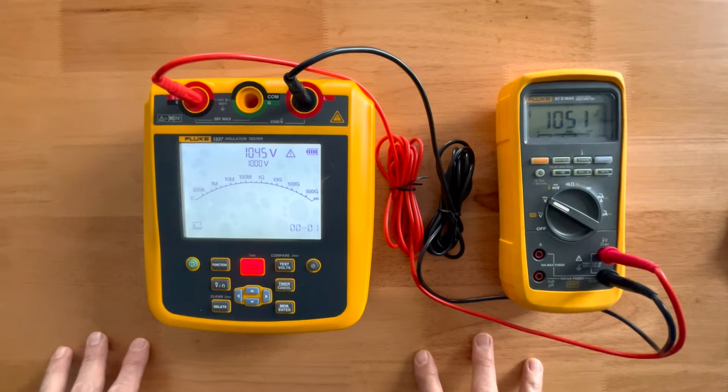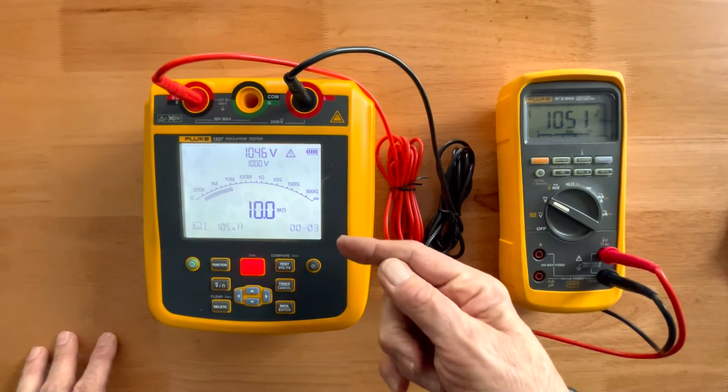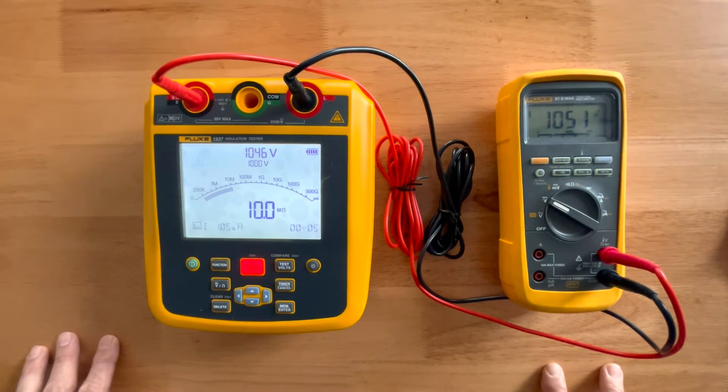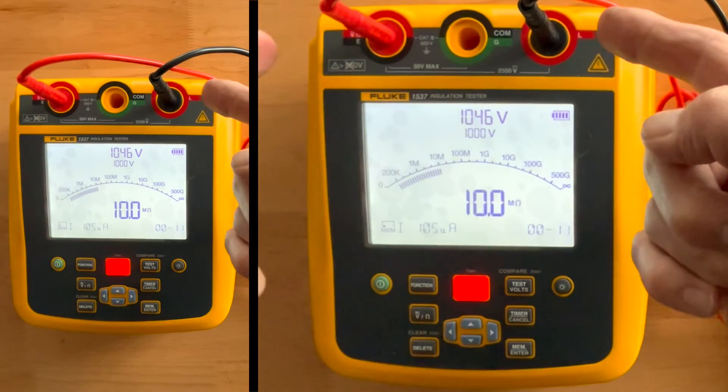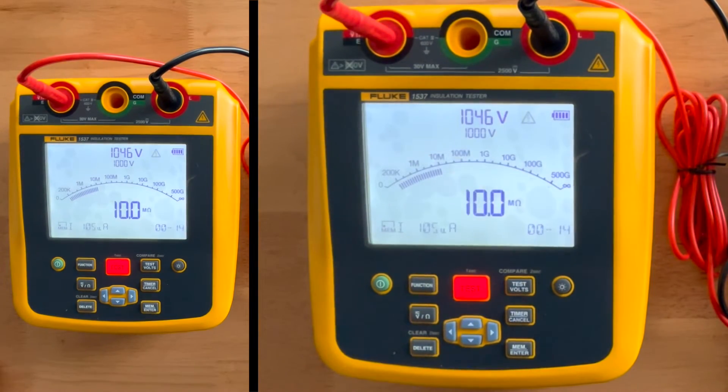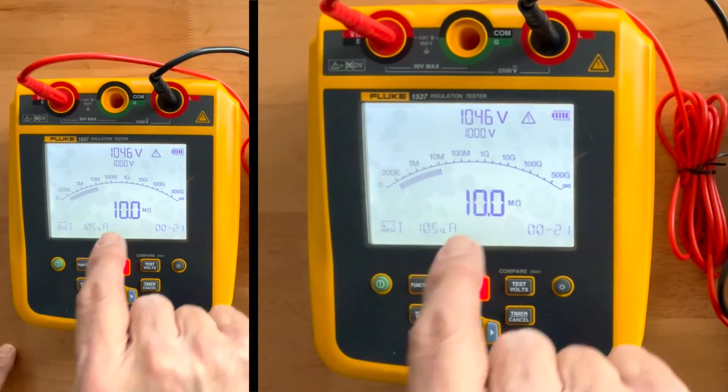So when I start the test, you'll notice immediately we light up in red. We also start counting out in time. And two things become immediately notable. First off, it is now flashing, telling me this is a live output off the terminals on the top. The range is 1,000 volts. We're actually outputting 1,046 volts. And I'm going to get both an analog indication as well as a digital readout.